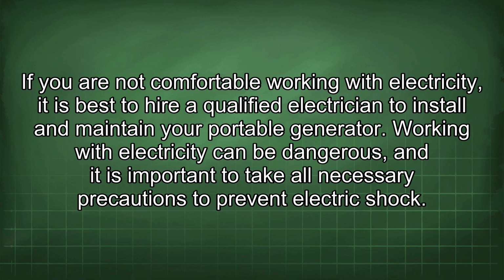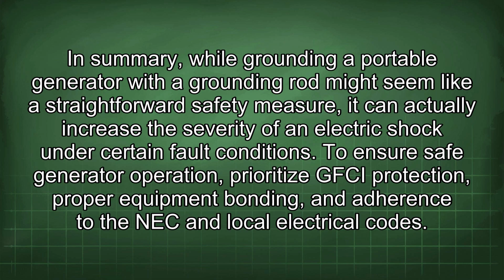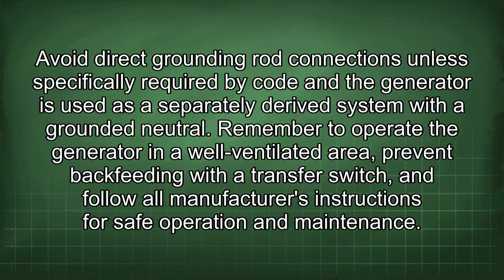electric shock. In summary, while grounding a portable generator with a grounding rod might seem like a straightforward safety measure, it can actually increase the severity of an electric shock under certain fault conditions. To ensure safe generator operation, prioritize GFCI protection, proper equipment bonding, and adherence to the NEC and local electrical codes. Avoid direct grounding rod connections unless specifically required by code and the generator is used as a separately derived system with a grounded neutral.